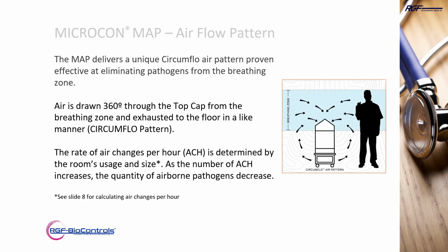I don't think this slide mentions it, but there are kits available. If we need to make this an isolation room or a positive or negative pressure room, we can block off one of the exhausts using what's called a block off kit, and run flex duct out the other exhaust to exhaust into the environment.